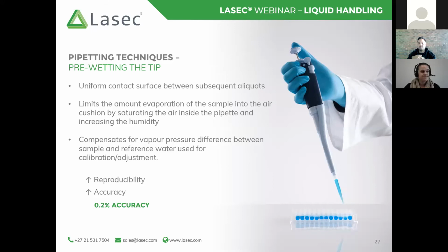And the reason why I don't enjoy the term pre-rinsing is if you're rinsing something, it's got the idea that you are trying to clean something out or remove something from the surface. Obviously, with pipettes and using disposable tips, we assume that those tips are clean and not being necessarily reused. And so you're not rinsing it for that purpose. Instead, you are actually just pre-wetting the tip. So the reasons we pre-wet that tip is, one, to create a uniform contact surface between subsequent aliquots. An aliquot is basically, if you are pipetting a volume, you could dispense smaller volumes, for example, those would be called aliquots, or it could just be each time you dispense a sample from the pipette.